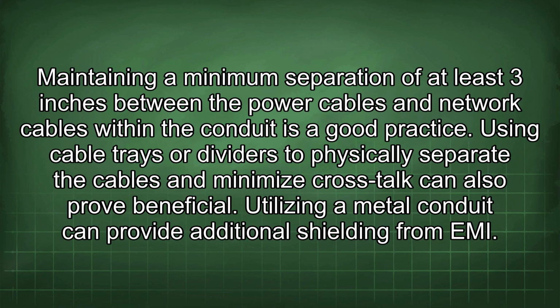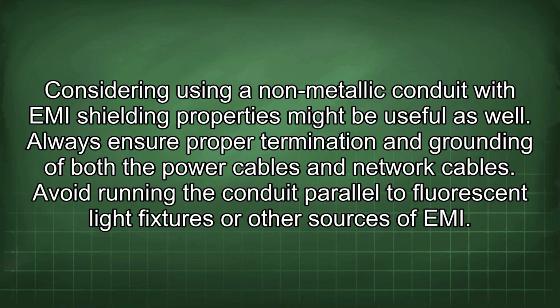Maintaining a minimum separation of at least 3 inches between the power cables and network cables within the conduit is a good practice. Using cable trays or dividers to physically separate the cables and minimize crosstalk can also prove beneficial. Utilizing a metal conduit can provide additional shielding from EMI. Considering using a non-metallic conduit with EMI shielding properties might be useful as well.